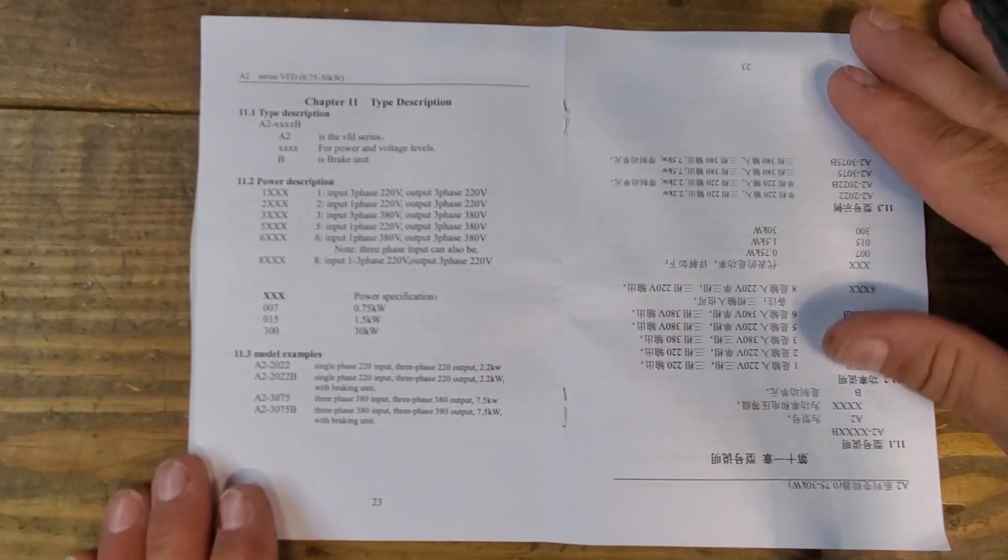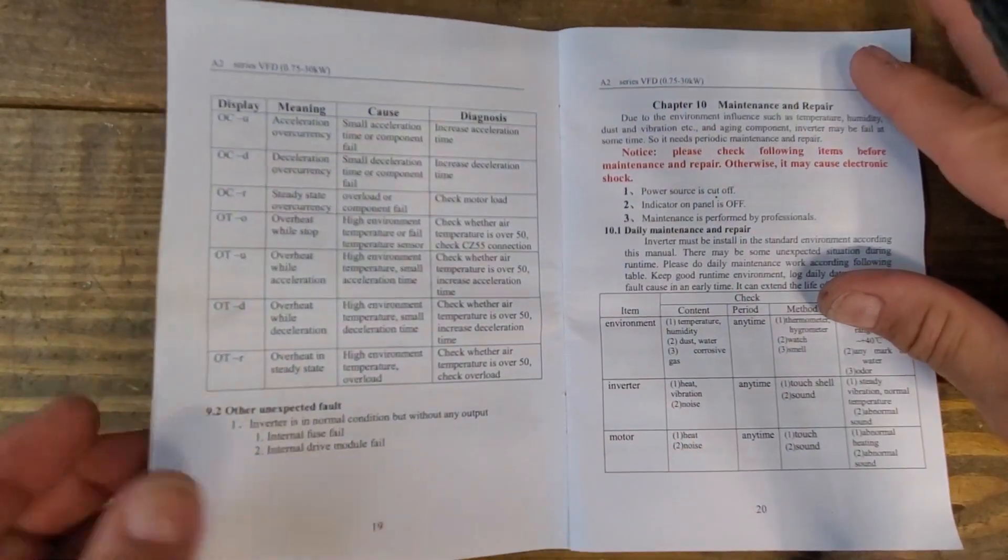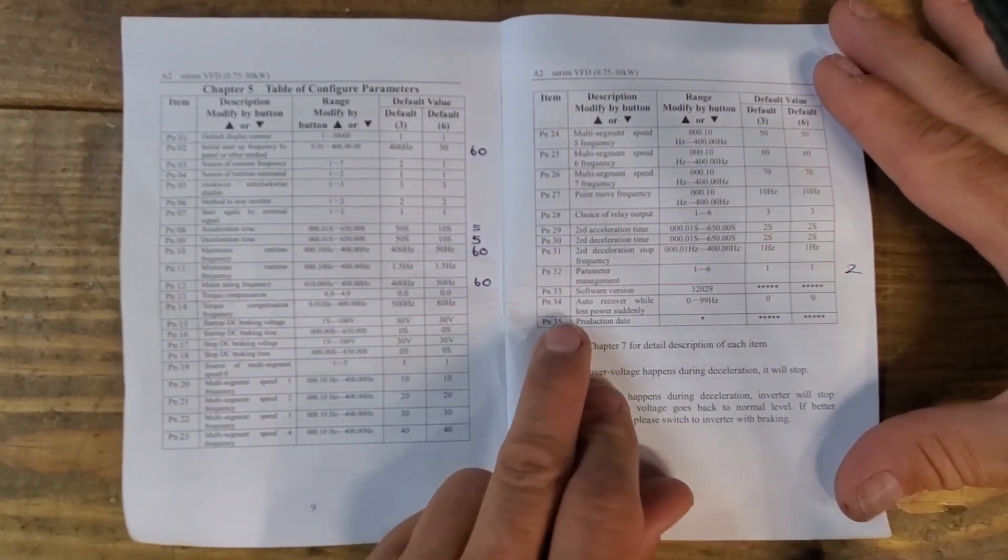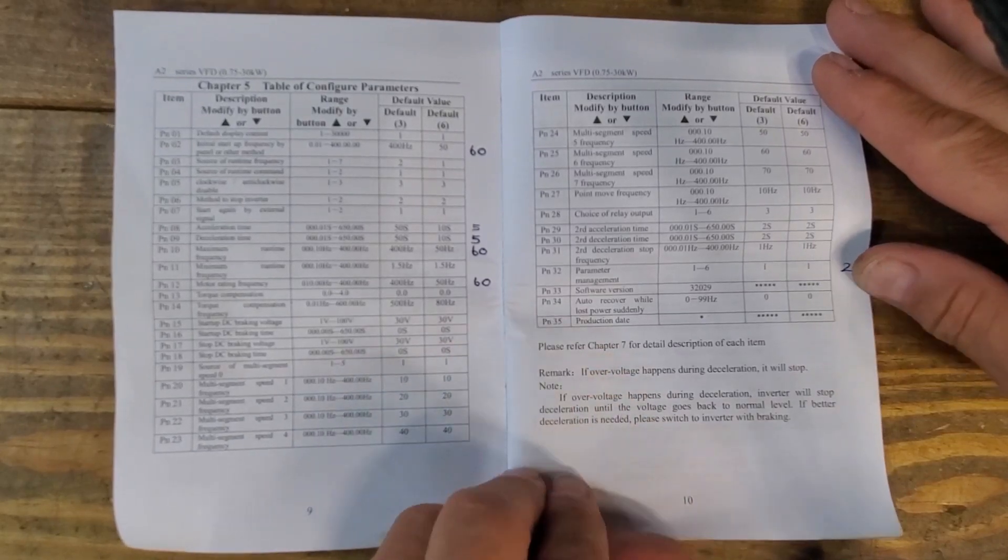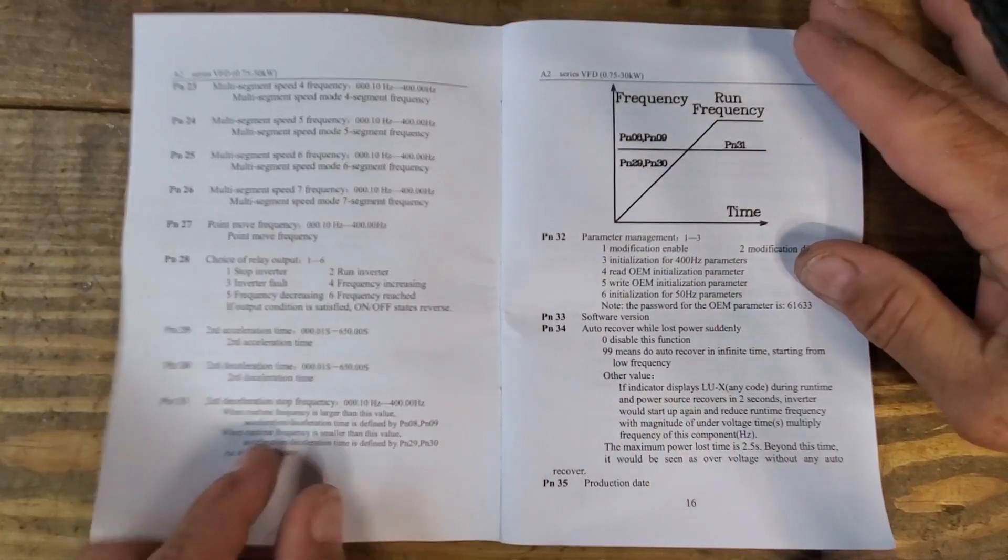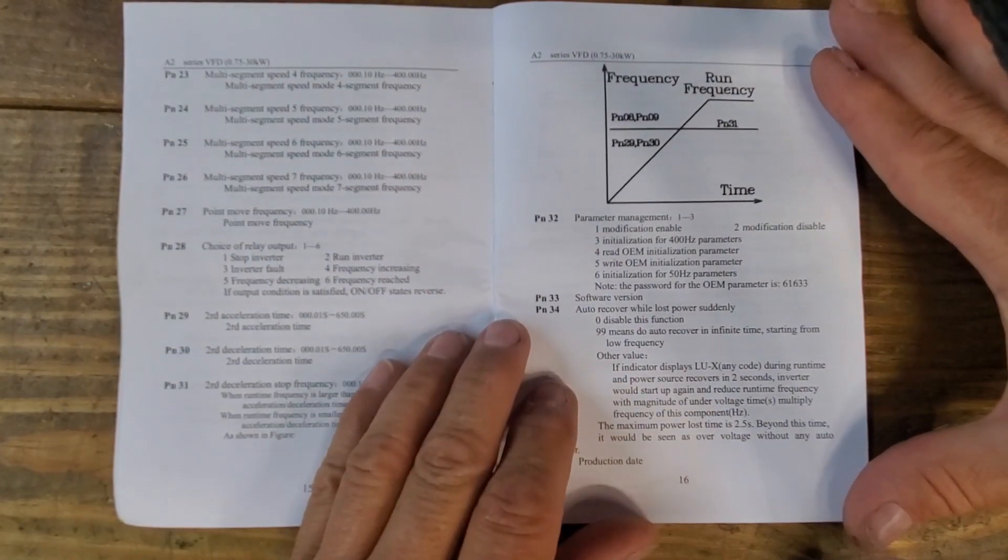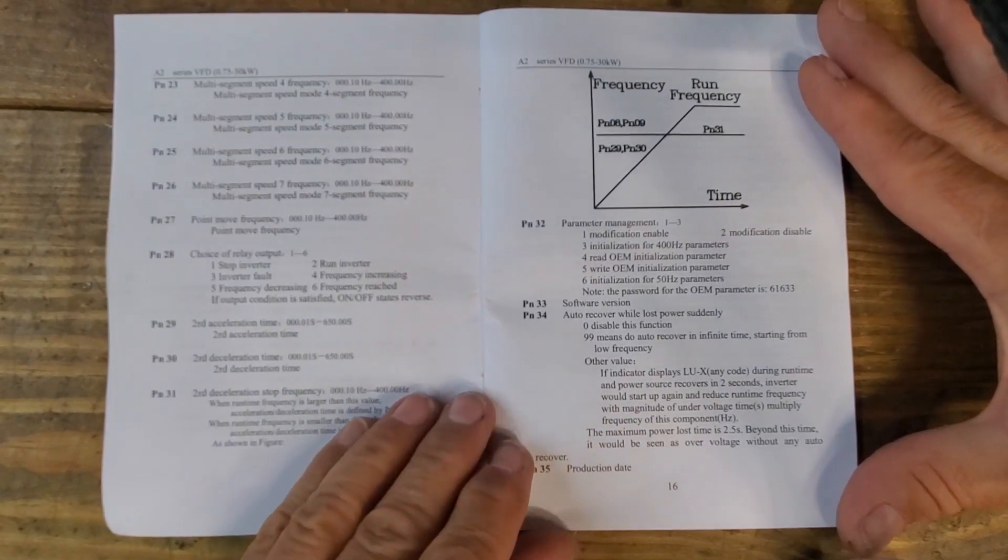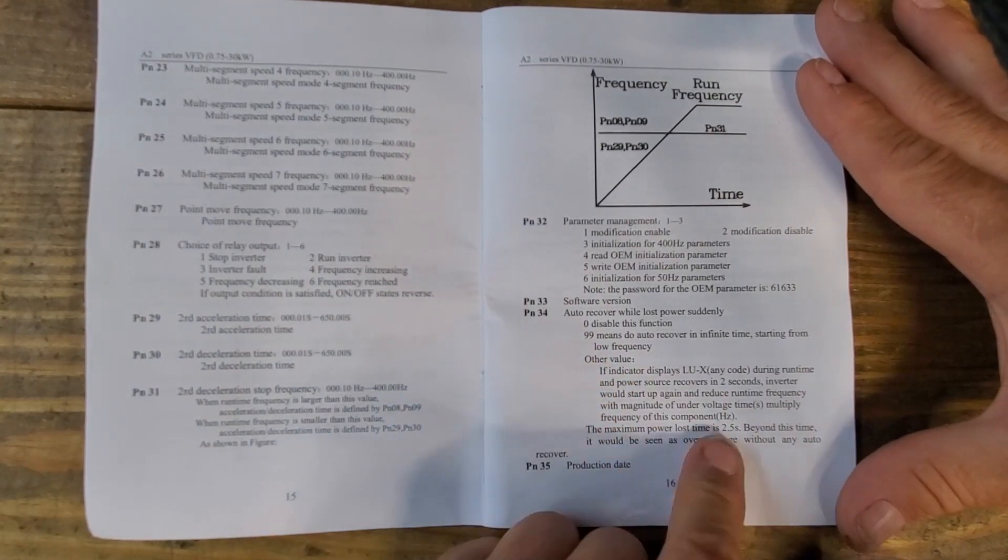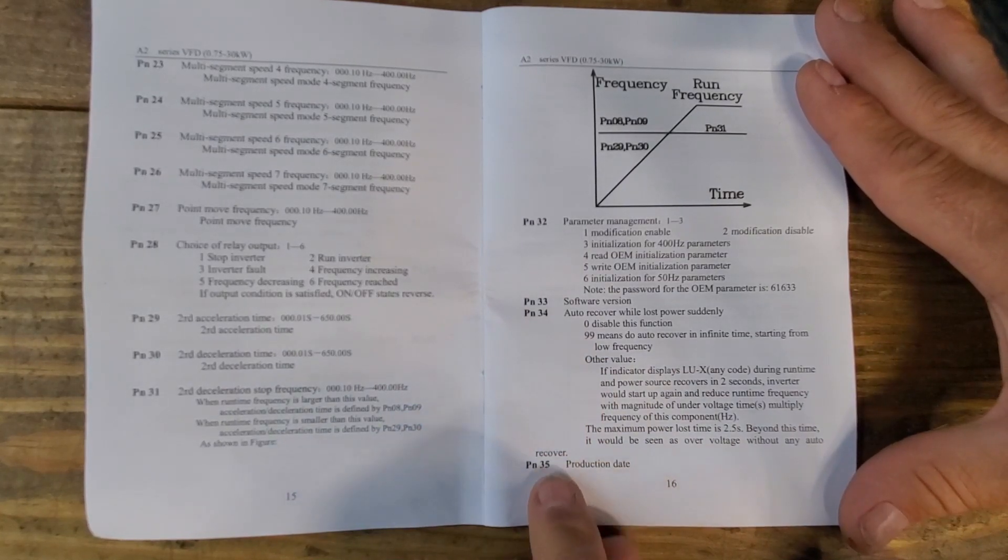And there we are. Now we're on to the Chinese part. One question that I did have. If I just come back. The PN34. If we look at PN34. Someone asked, can it be set so it will auto recover after a power loss? If you set PN34 to anything other than zero or 99, it should recover as long as the power comes back within two and a half seconds.